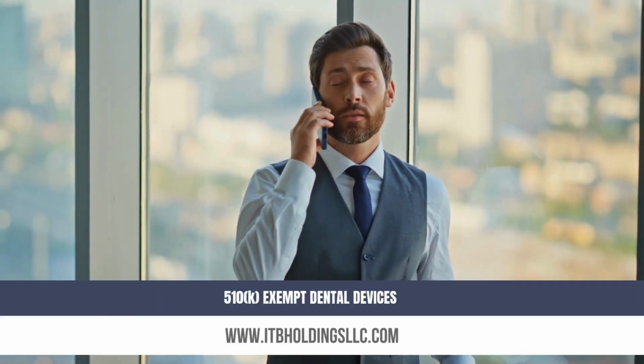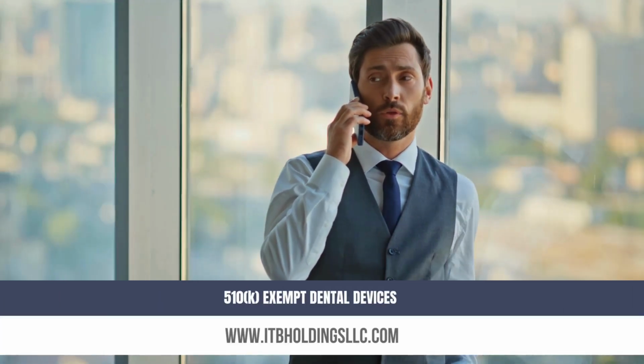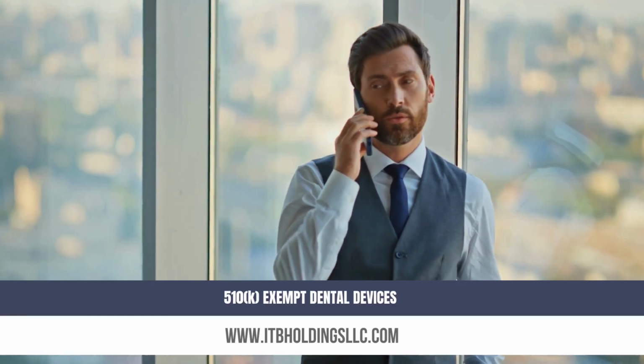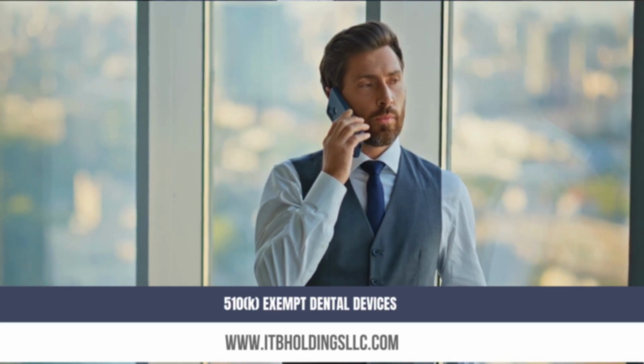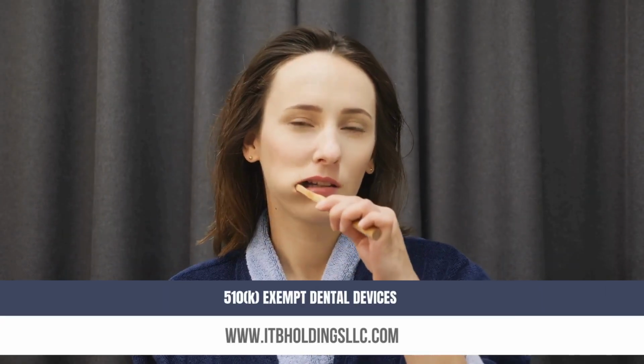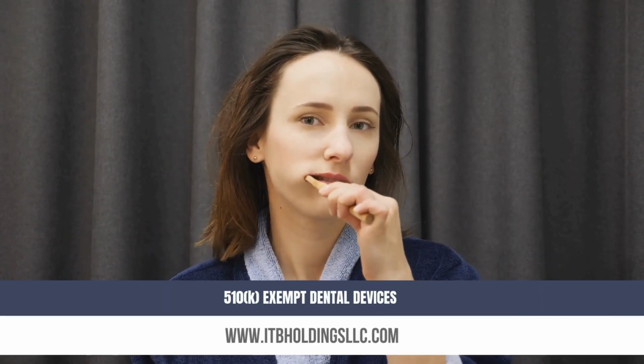Device classification depends on the intended use of the device and also upon indications for use. FDA has established classifications for approximately 1,700 different generic types of devices. If your device is classified as Class 1 or 2, and if it is not exempt, a pre-market notification 510(k) will be required for marketing. All devices classified as exempt are subject to the limitations on exemptions. Pre-market notification 510(k) and clearance are not required before marketing the following dental medical devices in the United States.